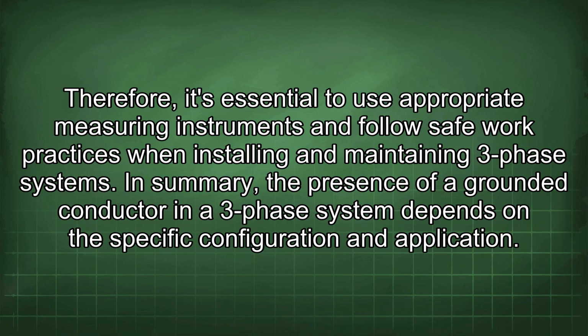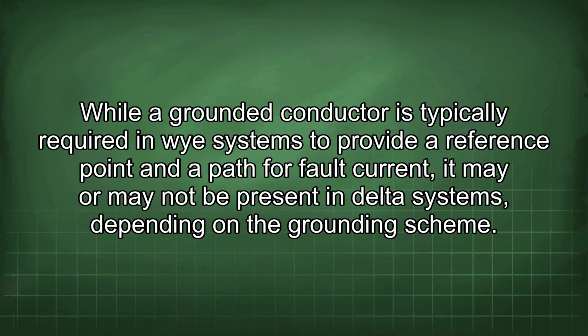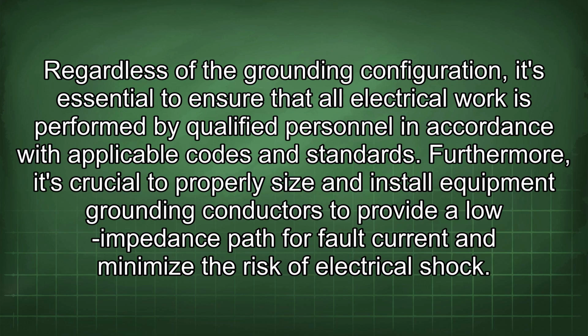In summary, the presence of a grounded conductor in a three-phase system depends on the specific configuration and application. While a grounded conductor is typically required in Y systems to provide a reference point and a path for fault current, it may or may not be present in Delta systems, depending on the grounding scheme. Regardless of the grounding configuration, it's essential to ensure that all electrical work is performed by qualified personnel in accordance with applicable codes and standards.